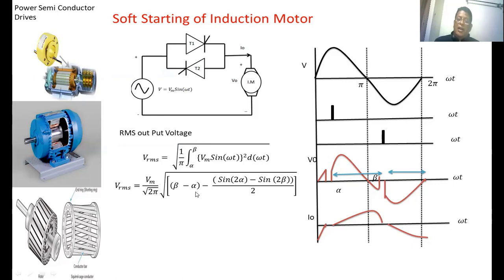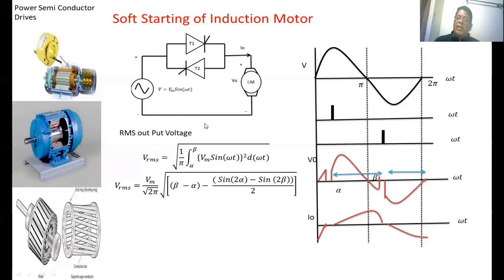The minimum firing angle is alpha equal to the load angle, and you can vary the firing angle alpha up to pi. Now, what is meant by soft starting? At the time of starting, the induction motor will take a large amount of current. By means of anti-parallel SCRs we are going to start the induction motor. To reduce the starting current, we apply a small voltage to the induction motor by maintaining the firing angle of the two anti-parallel SCRs near to 180 degrees. Very less voltage is applied so the motor starts slowly. As the speed of the induction motor increases, we decrease the firing angle down to alpha equal to phi, increasing the voltage until the rated voltage is applied. This type of starting is called soft starting of an induction motor.